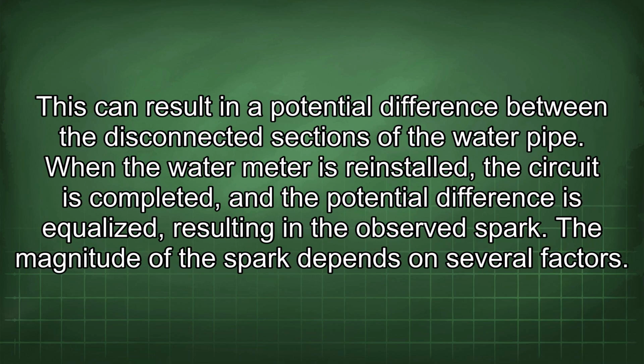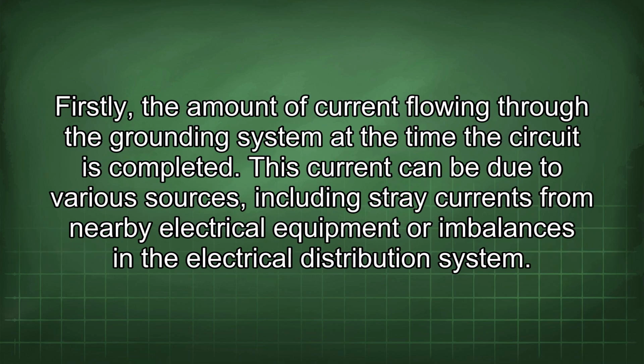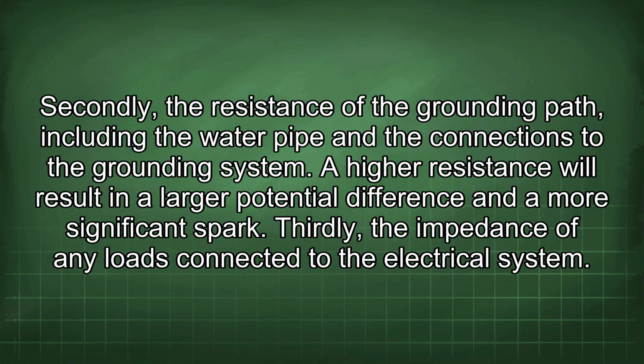This can result in a potential difference between the disconnected sections of the water pipe. When the water meter is reinstalled, the circuit is completed, and the potential difference is equalized, resulting in the observed spark. The magnitude of the spark depends on several factors. Firstly, the amount of current flowing through the grounding system at the time the circuit is completed. This current can be due to various sources, including stray currents from nearby electrical equipment or imbalances in the electrical distribution system. Secondly, the resistance of the grounding path, including the water pipe and the connections to the grounding system.